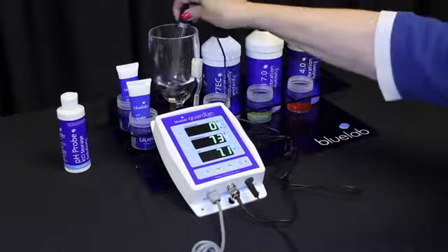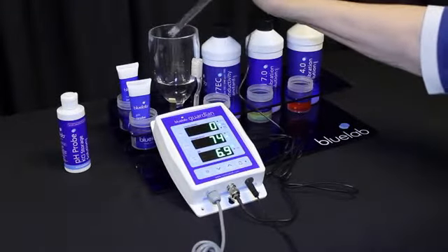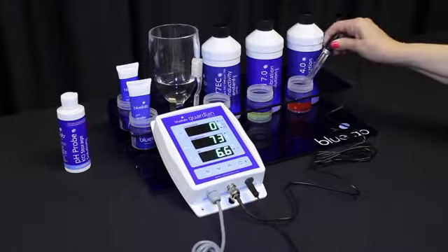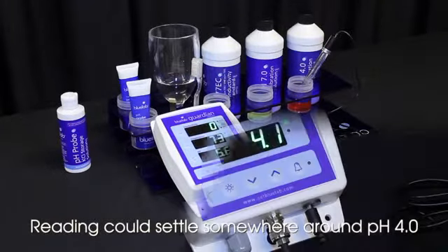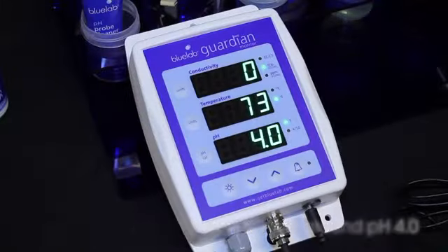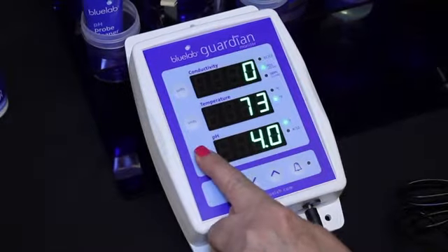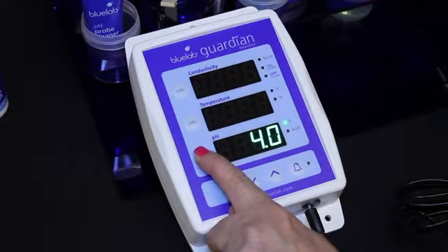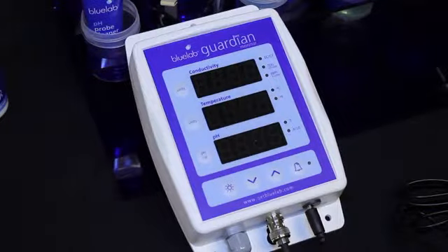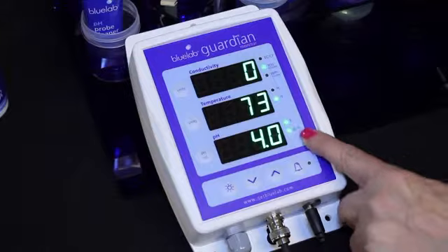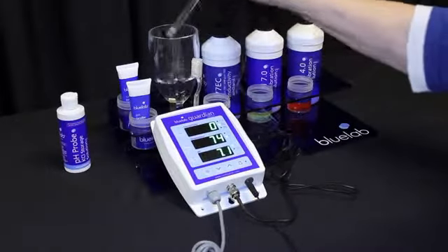Rinse the probe tip in clean tap water and place in pH 4.0 solution. Be patient and wait for the reading to stop. Remember, it may take a few minutes. Press and hold the pH cal button until pH and cal appear. Release. 4 will flash on the pH display. Then the pH 4.0 indicator light will glow.